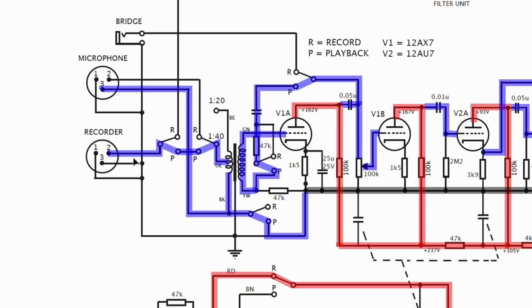Okay, so playback, you've got the signal from the recorder, comes in here, goes into the primary of this transformer, referenced to ground. Yeah, playback is single-ended input, as you can see over here, because your 1 and your 3 are common. That goes to ground, so that's all ground over here. So playback, you've got single-ended input, a reference to ground, signal comes in, goes in here, goes through there, into the transformer. Transformer's referenced to ground, okay, that's fine. And then the signal is produced over here, raised from ground through that resistor.